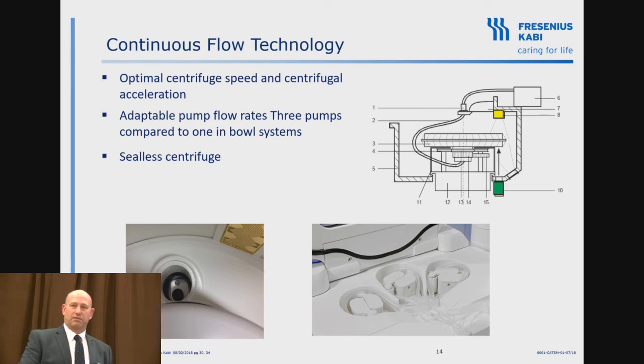I always like to do the tortoise and hare scenario. We can produce, on our highest speed, 100 mils a minute of product, of PRC coming out. Granted, the reservoir is not going to drop really fast like a bowl system. The bowl system is going to drop that and stop into wash, and then it's going to drop and empty, and then it's going to drop again when it starts filling again. Ours is continuous. Like I said, it's like the tortoise and the hare. We will catch up, and at the bottom, depending on the hematocrit we're processing, we're as fast or faster.